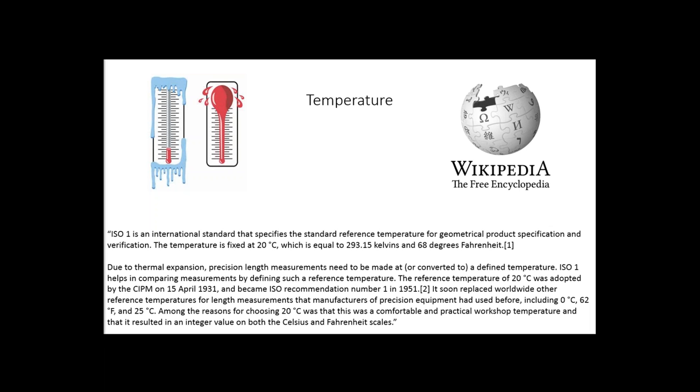Your machine all by itself can be perfectly in spec at 110 degrees as long as it was calibrated at that temp and the artifact used for said calibration was at its correct calibrated temp, and the temp of the room and device stays the same. Anything you measure that has thermal expansion capabilities, everything in other words, will change its true shape at that temp, and your real-world readings will be skewed.